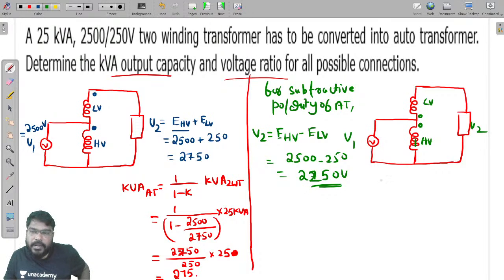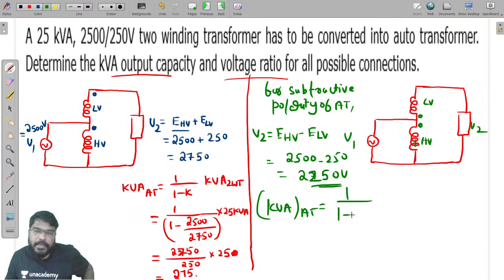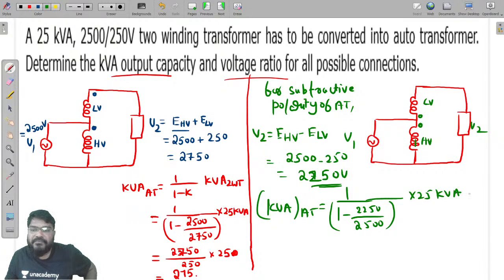Now let us find K here, the transformation ratio. The kVA of auto transformer equals 1 minus (low voltage 2250 divided by 2500), multiplied by 25 kVA. Simplify this and you get the answer: 250 kVA.